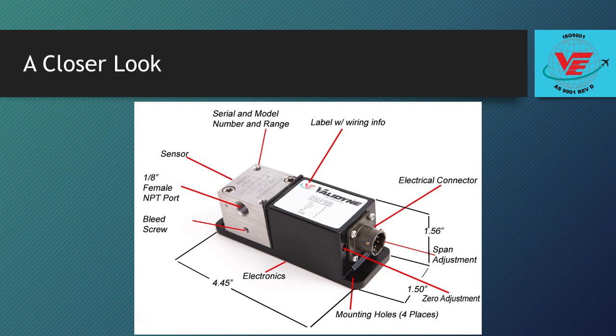The P55 also comes with a 5/16 inch AS5202/1, ZTA41, and custom pressure port configurations. In the differential model shown here, the P55 will have 2 1/8 NPT female ports on each side of the sensor body. These are marked plus and minus. There is also a bleed screw opposite each pressure port to allow the bleeding of air trapped inside the 2 sensor cavities. This allows the P55 to be used in dynamic measurement applications.